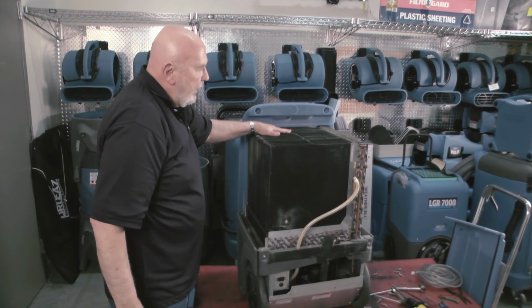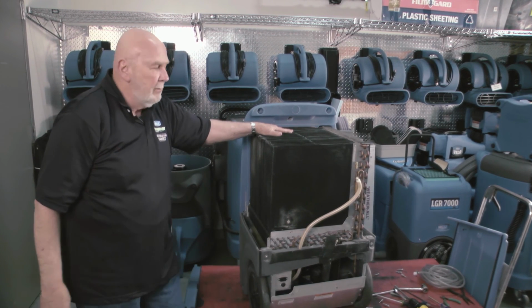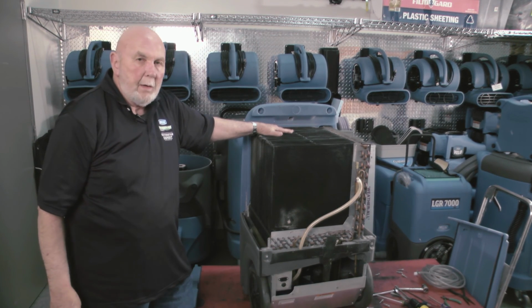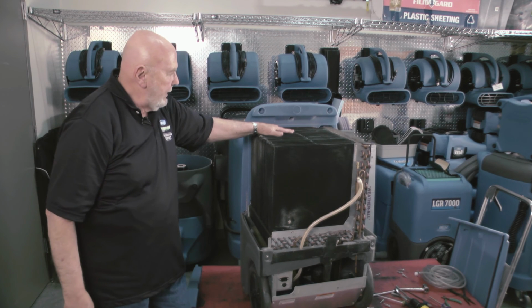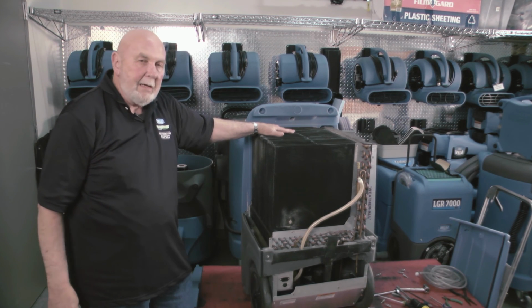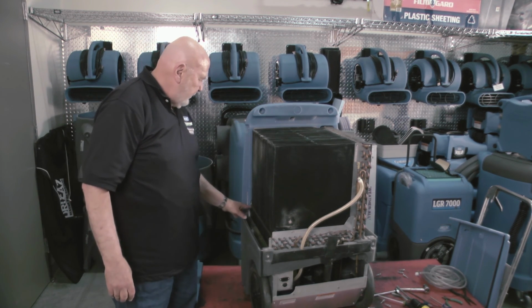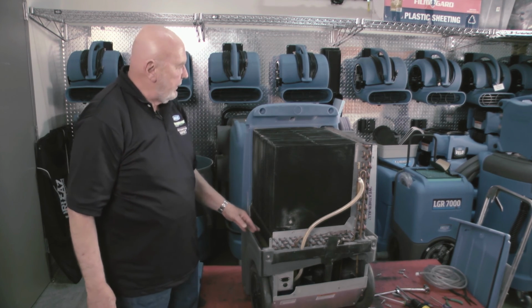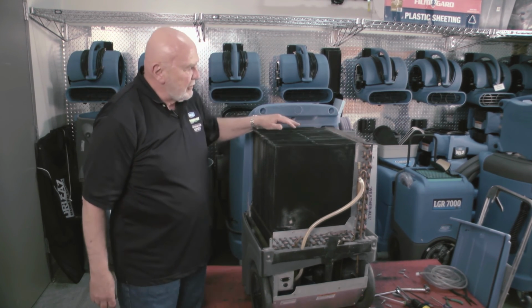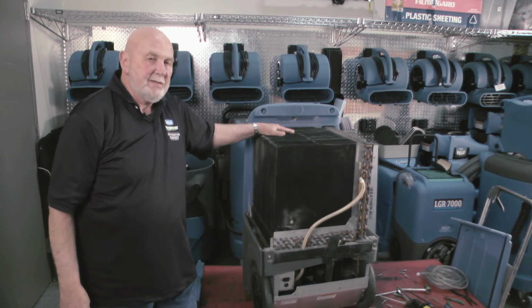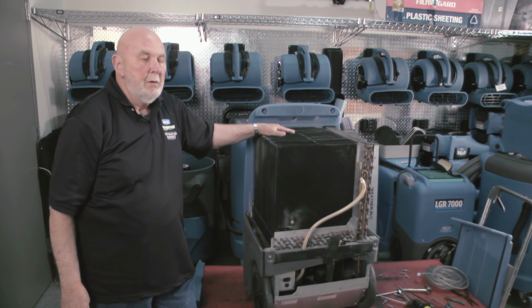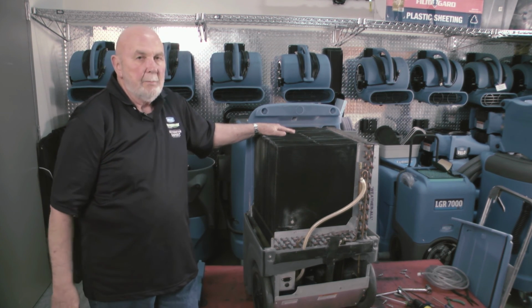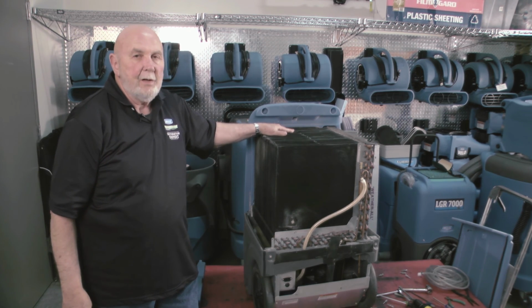Next you have the heat block, and you want to pay attention to the orientation it's in—put it back in the same way. Always pay attention to all of the gaskets and make sure they are in correctly, because they determine the airflow of the unit, which is essential to both drying and the operation of the unit.